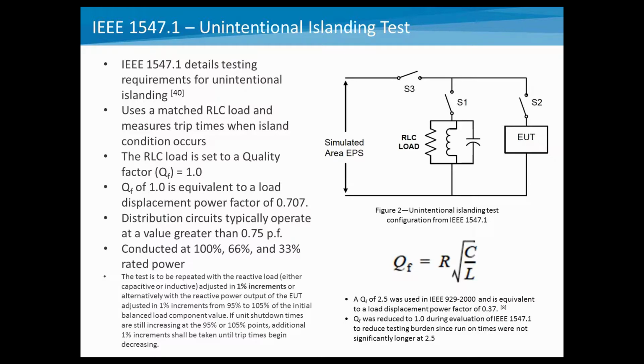A couple things to realize on this is that you do have what is considered the worst condition that you can create to understand how well the anti-islanding techniques work. So this RLC load is very exactly matched to the output of the unit under test. It's done at 100%, 66%, and 33% of rated power. It's also quite difficult to detect exactly when you have that match condition, so it's done in 1% increments, around 95 to 105% of the loading conditions.